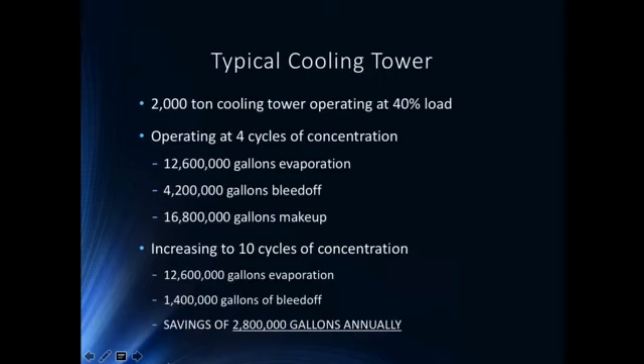So how do we save water in a cooling tower? Because, as I said, the 12.6 million gallons is a function of the heat load. That doesn't change depending on how many cycles you're running, or on how good we're doing from a water treatment standpoint. It's a function of the heat load of the building. So if we increase from 4 cycles to 10 cycles, which is what we typically run, 10 to 12 cycles of concentration, the evaporation doesn't change. It's still that same 12.6 million gallons. However, we now are only going to have to bleed off 1.4 million gallons. So right there, that change in this 2,000-ton tower operating at 40% load, by going from 4 cycles to 10 cycles, 2.8 million gallons of water is saved just in that one change, which again puts you a long way towards some of these 20% goals.